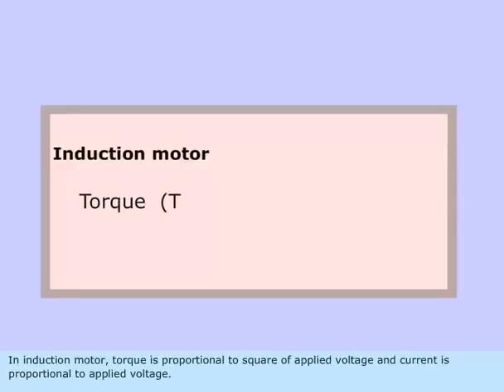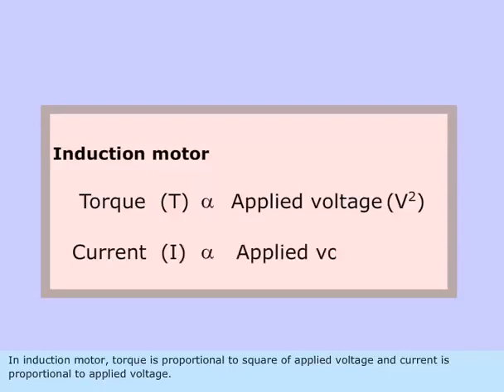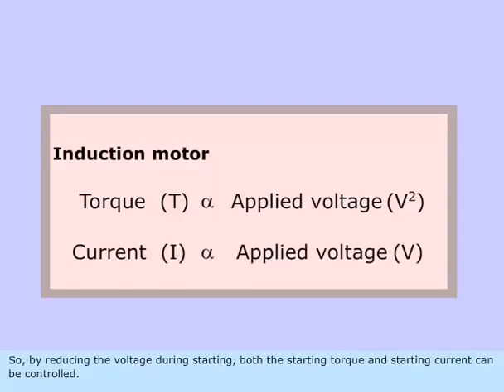In induction motor, torque is proportional to square of applied voltage and current is proportional to applied voltage. So by reducing the voltage during starting, both the starting torque and starting current can be controlled.